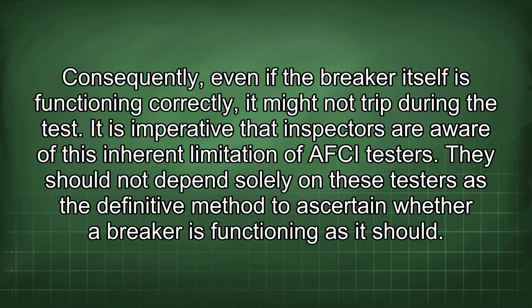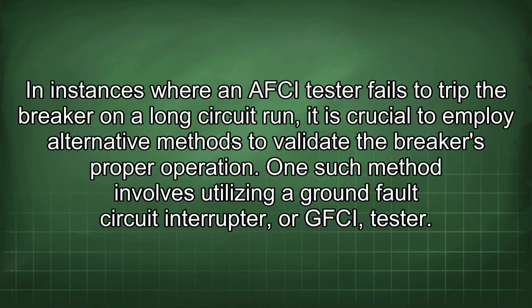It is imperative that inspectors are aware of this inherent limitation of AFCI testers. They should not depend solely on these testers as the definitive method to ascertain whether a breaker is functioning as it should. In instances where an AFCI tester fails to trip the breaker on a long circuit run, it is crucial to employ alternative methods to validate the breaker's proper operation.